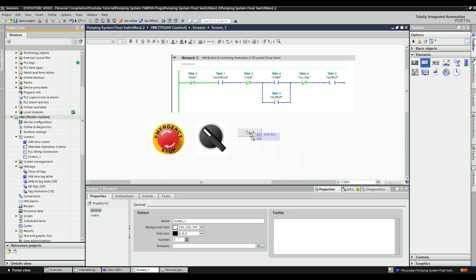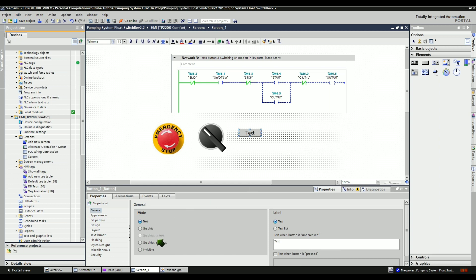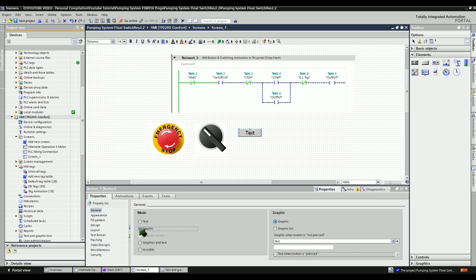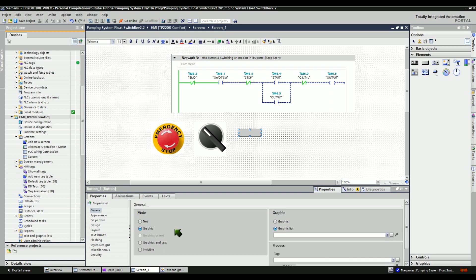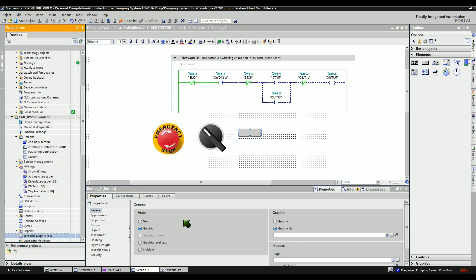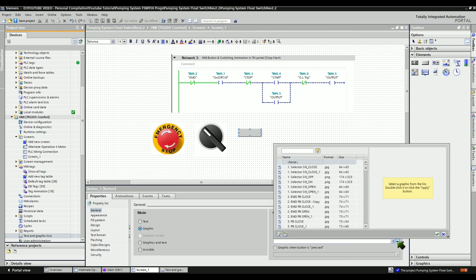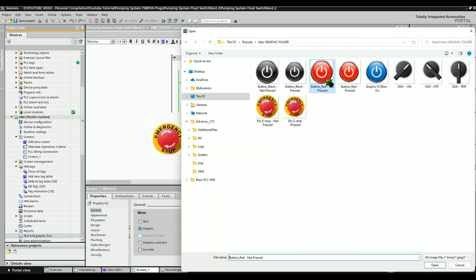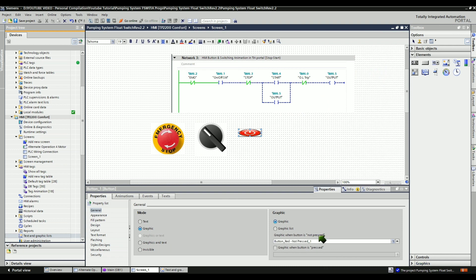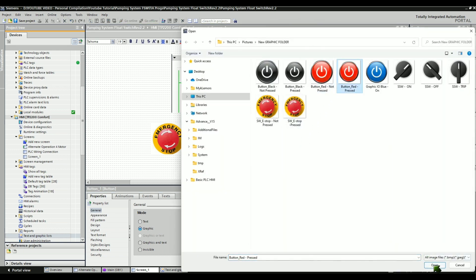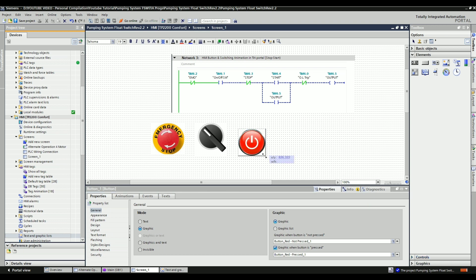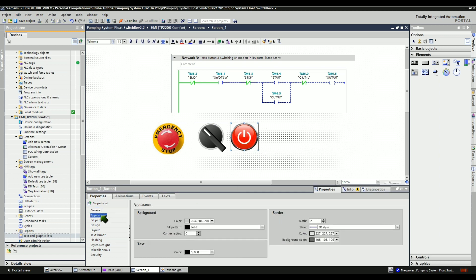Just click the button and drag and drop it into the working area of the screen. Under General and Properties, change the mode format to 'Graphic.' You can also choose 'Graphic and Text' if you want. There are two possible ways to create button animation: if you choose 'Graphic List,' you have to create a graphic list in the text and graphic lists folder. If you choose 'Graphic,' click here to open the selection dialog for the graphic when the button is not pressed. If not available, create a new graphic from file. Check the box to open another graphic selection dialog for when the button is pressed. Align and resize the graphic, and change the appearance and design color to match the screen background.